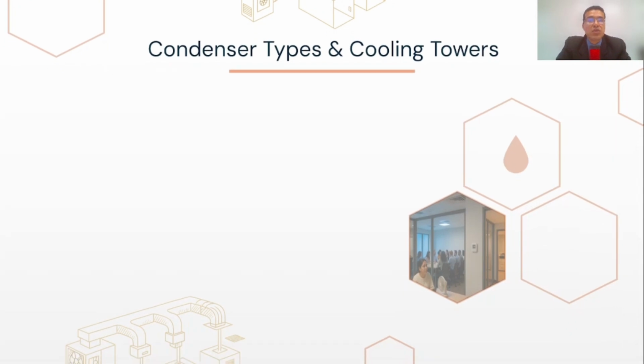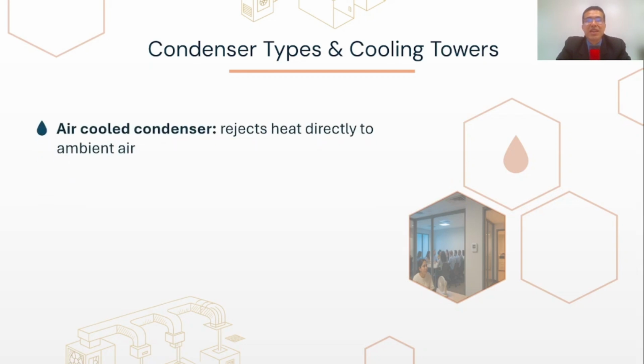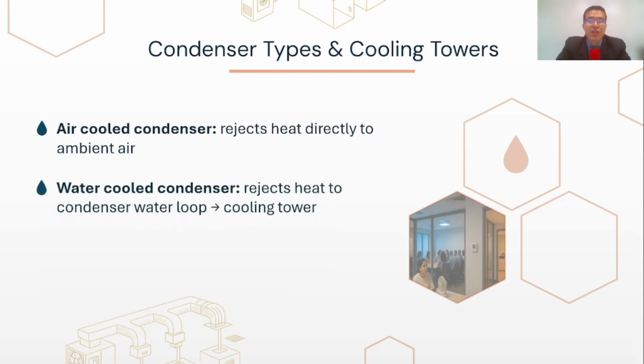We have just reviewed how different HVAC architectures handle heat rejection, particularly in packaged units. Now let's look closer at the two primary methods for heat rejection, air-cooled and water-cooled, and examine the role of cooling towers, a critical component in larger water-cooled systems. Air-cooled condensers are typical of packaged systems and smaller plants, while water-cooled condensers require a condenser water loop and a cooling tower for heat rejection, common in larger central plants.